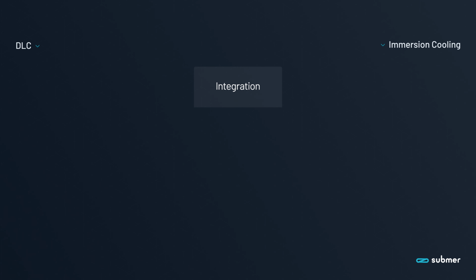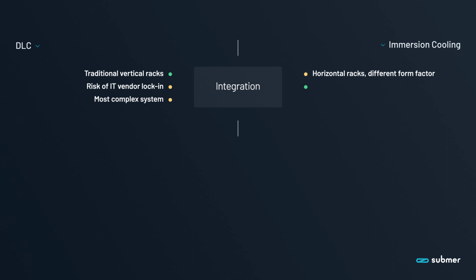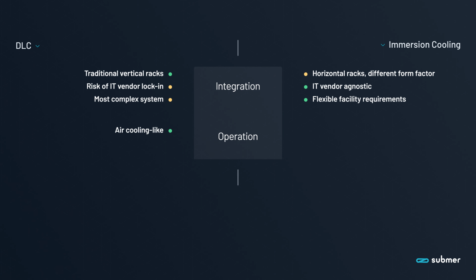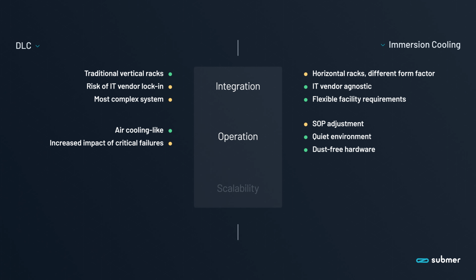Direct-to-chip cooling uses a traditional rack form factor, but it carries vendor lock-in risks and increasing complexity. In contrast, immersion adopts a different form factor, is vendor-independent, and allows for flexible facility requirements. Operation of DLC is more similar to air cooling, but comes at the expense of higher critical failure impact. Immersion requires some procedural adjustments, but it is quieter and dust-free.